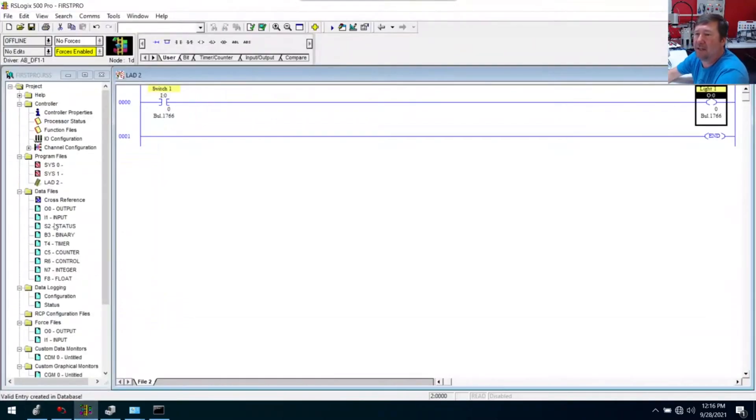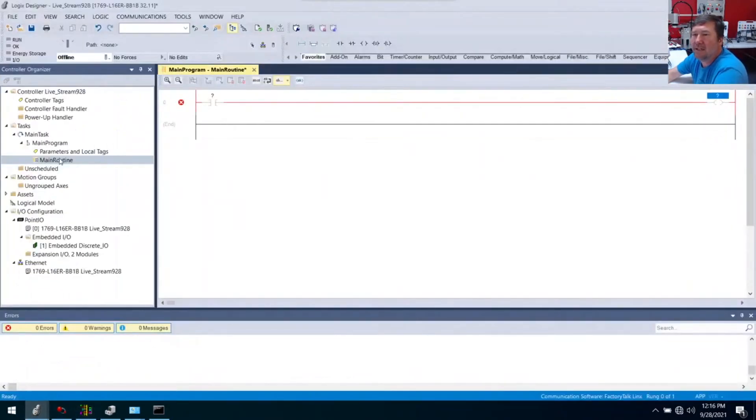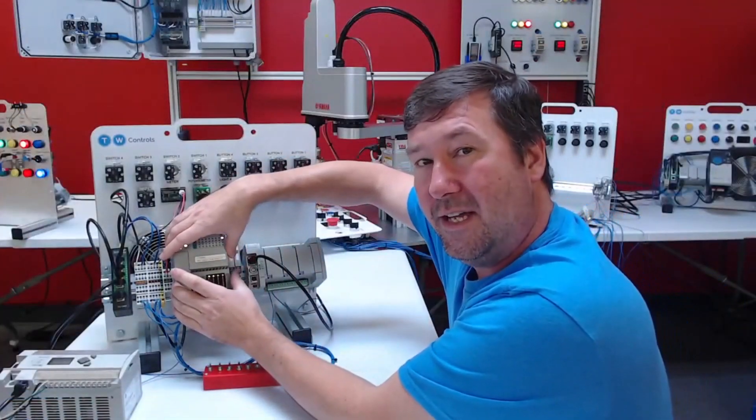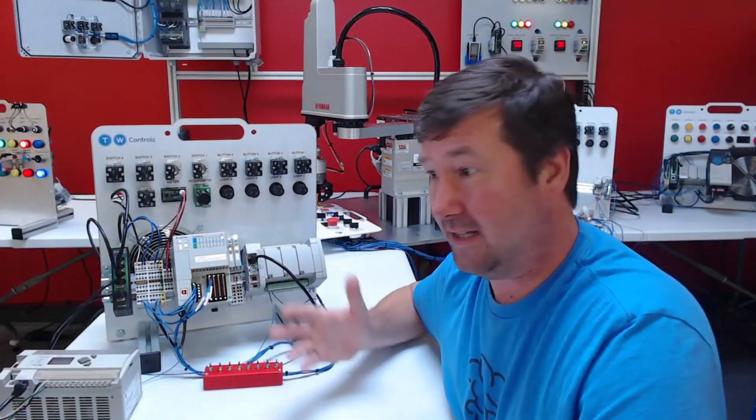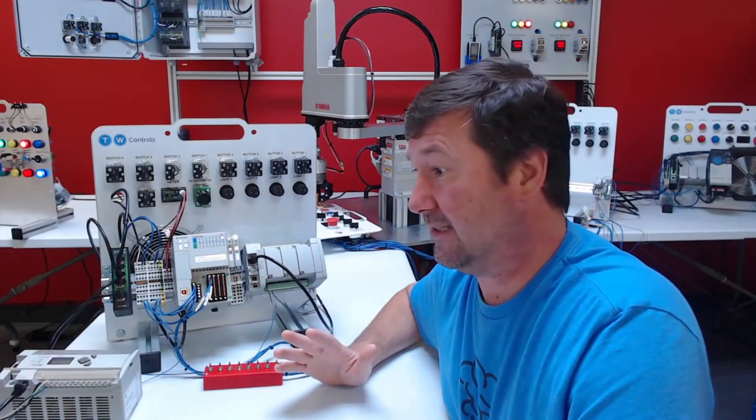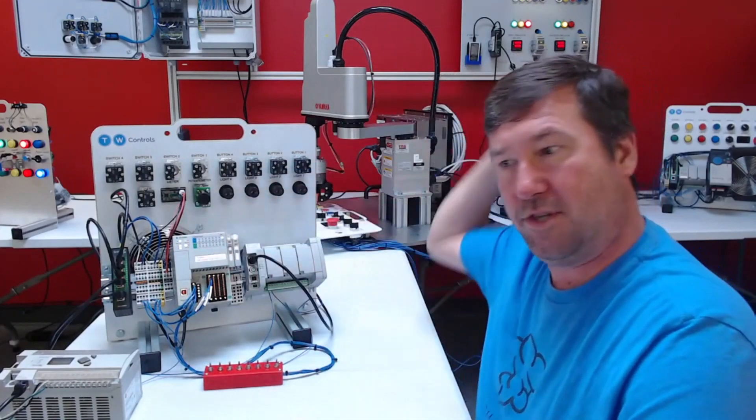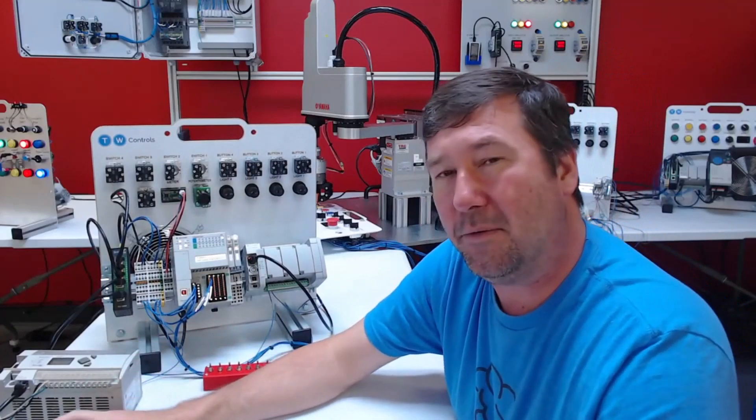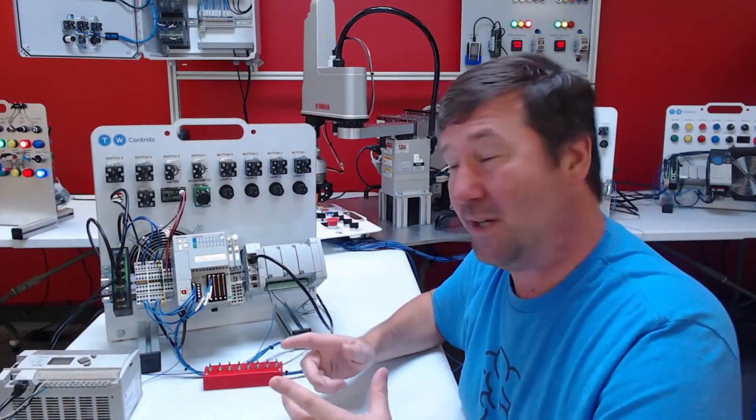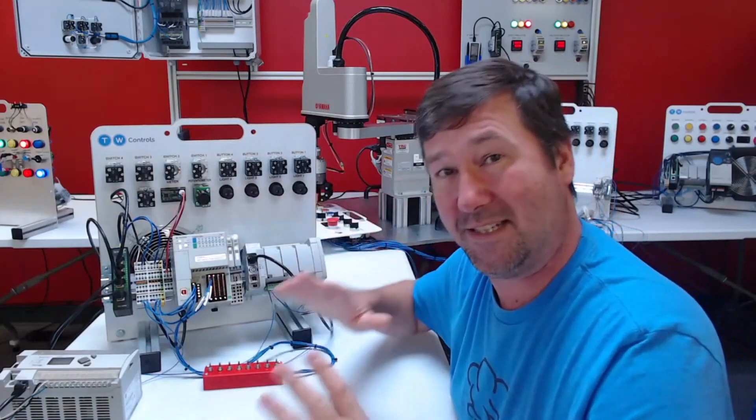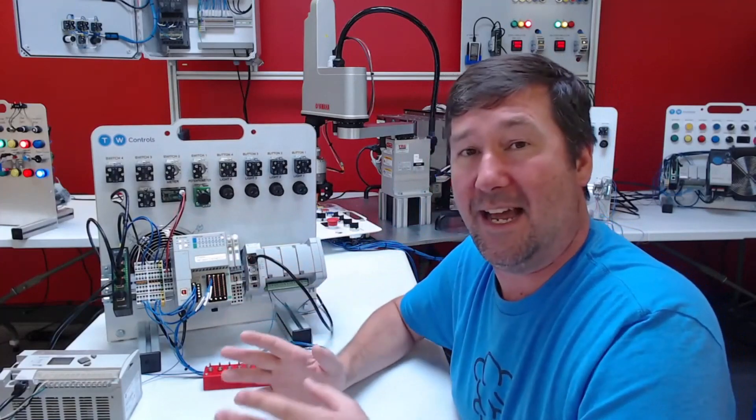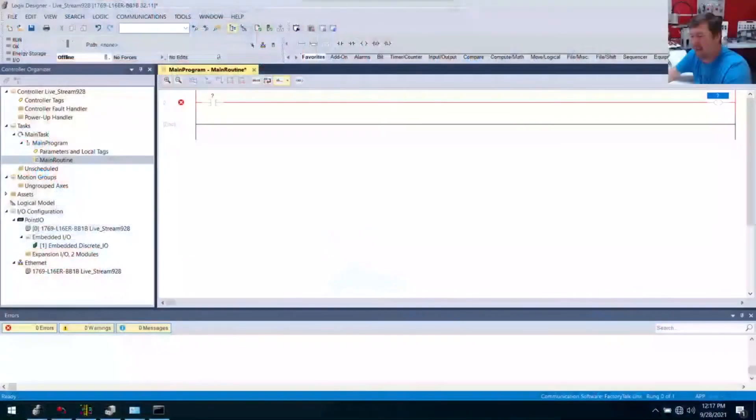Over here it was pretty easy. We were able to figure out, there's our inputs, there's our outputs, drag some things down, we're ready to download. Studio 5000 is a little different because obviously you don't see your inputs and outputs laid out really well there. While the input and output works great if the I/O is right there, when you got into data highways and all these other networks in 500 and everything, it became nightmarish because you couldn't figure out whether an output was on this PLC or whether it was shooting over DeviceNet. While it's really complicated to figure out where your first input and output are in the compact Logix, it is insanely easy to look at a tag address and figure out where it is.